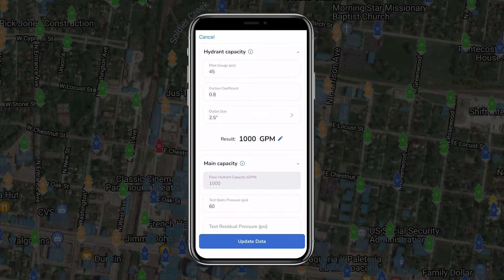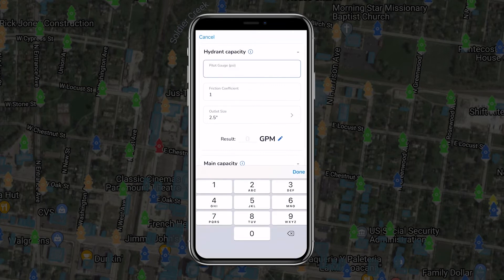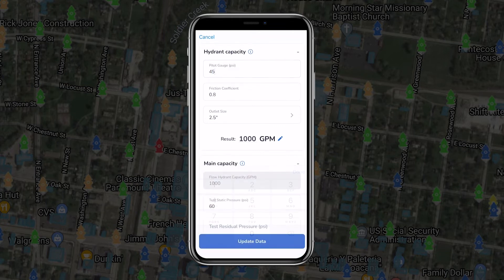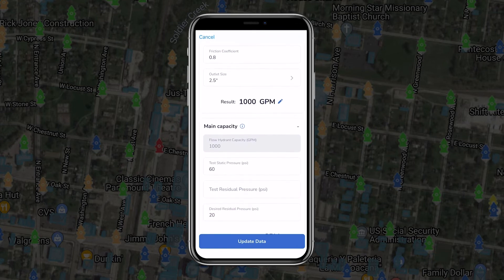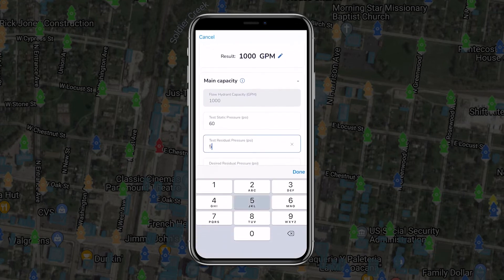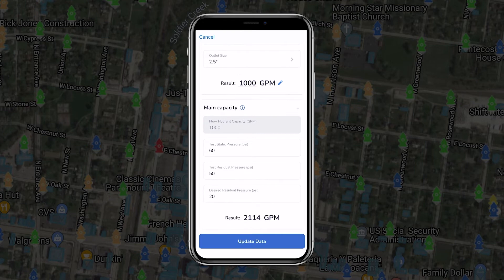Before opening the hydrant valve to test the pressure, the team member at the flow hydrant should alert the team member at the test hydrant that they'll be opening the valve. When the flow hydrant is fully open, both members will simultaneously record the pressure from the pitot gauge on the flow hydrant and the residual pressure at the test hydrant.